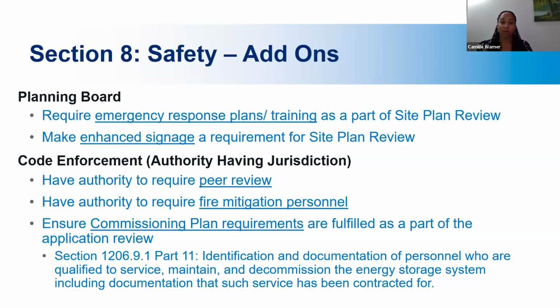The next recommendation is that planning boards make enhanced signage a requirement for site plan review. This includes signage beyond the battery energy storage unit itself, covering perimeter fences or security barriers, ideally with a map of the site, locations of enclosures and associated equipment, 24-hour emergency contact information, and hazard warnings, to improve safety and communication for emergency responders and the public.